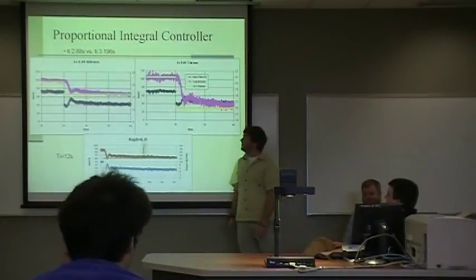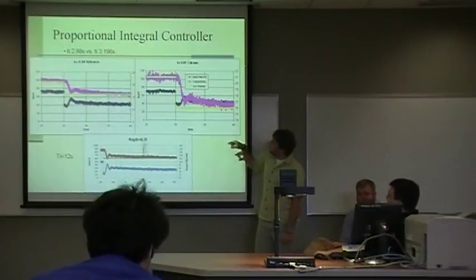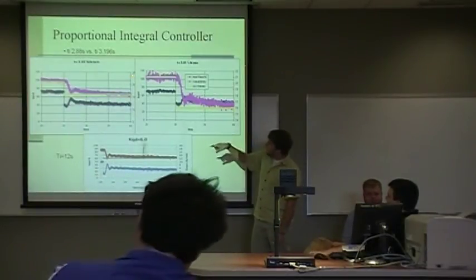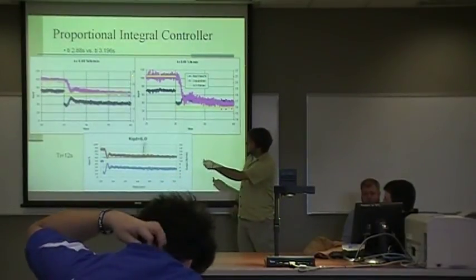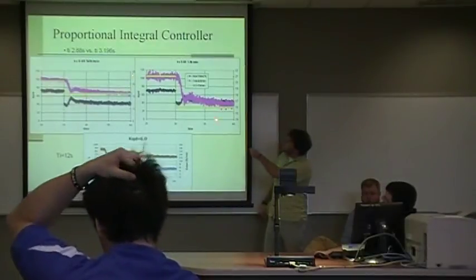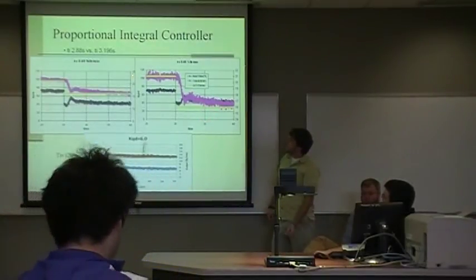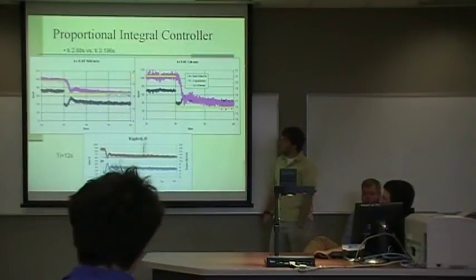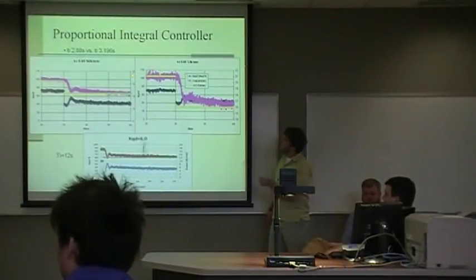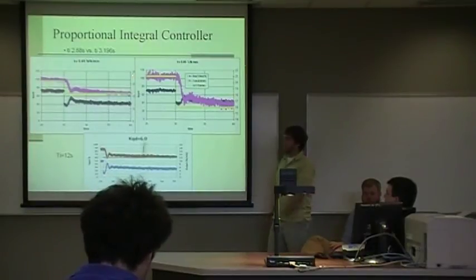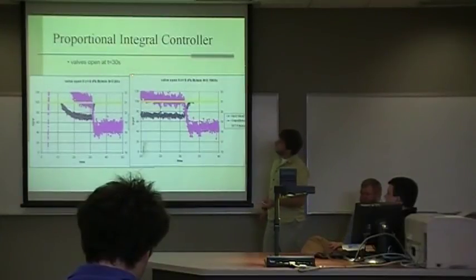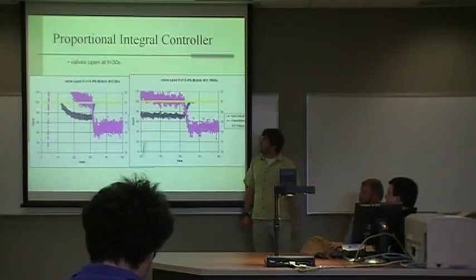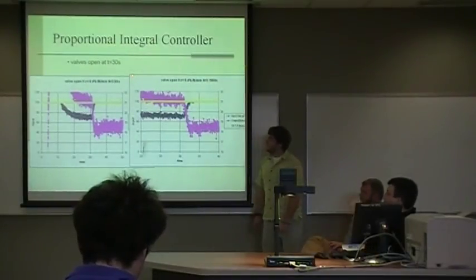So these are the comparisons for the TI of 12 and the TI of 2.88 is in this one, and the TI of 3 is this one. You can see the graphs are a little bit different as you change the TI. And this is all for a KC of 5.85, just changing the TI. And this is the valves open with a KC of 8.4, comparing the two different TIs. They're pretty much the same.